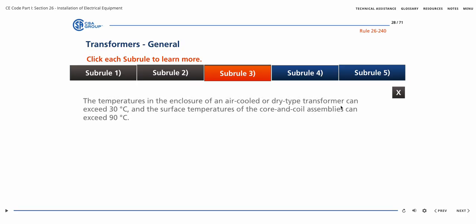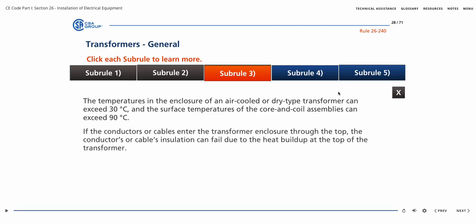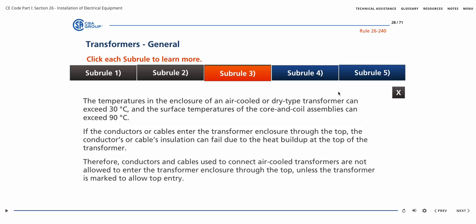Subrule 3 recognizes that the temperatures in the enclosure of an air-cooled or dry-type transformer can exceed 30 degrees Celsius, and the surface temperatures of the core and coil assemblies can exceed 90 degrees Celsius. If the conductors or cables enter the transformer enclosure through the top, the conductors or cables insulation can fail due to heat buildup at the top of the transformer. Therefore, conductors and cables used to connect air-cooled transformers are not allowed to enter the transformer enclosure through the top, unless the transformer is marked to allow top entry.